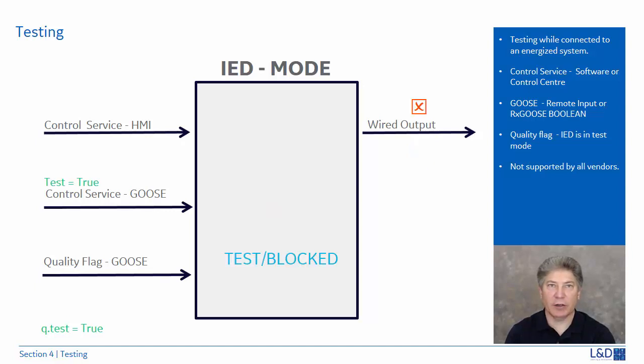The next mode is test blocked. Here we have the test equal to true, the Q.test bit is set to true, but there are no contact outputs. The mode is useful while performing tests while the device is connected to a live system. So with all this confusion, not all the vendors were supporting this form of testing. In the next section, we'll take a look at the revised way of doing testing.